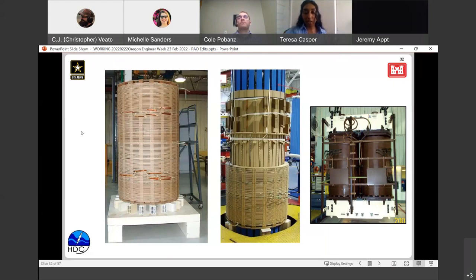This is showing the internals of your transformer. These are windings, and in that middle picture you can see the concentric circles that a winding is wound in. What's really interesting about transformers is almost 90% of what they put inside this large piece of equipment is done by hand. Someone by hand wraps those windings, which are basically copper bars wrapped in paper. Part of what we do at HDC is observe them doing this work at a factory, which is really cool.